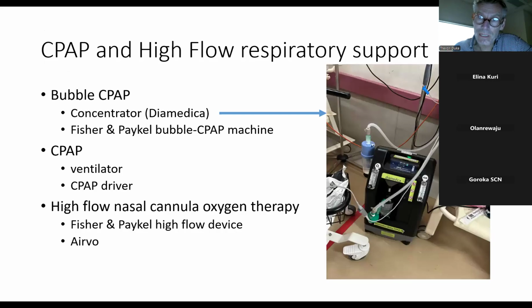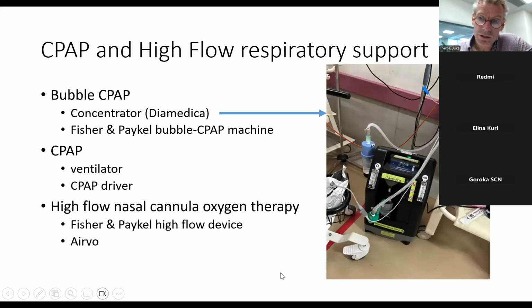This is the Diamedica machine that is being introduced in many hospitals. It's a similar machine to the grey one that we previously had used more in children than neonates, but most of these are going to be delivered to special care nurseries and neonatal units in provincial level hospitals. I'll talk quite a bit about how these work, but there's an oxygen concentrator that extracts atmospheric air, removes the nitrogen, and produces both oxygen and air. Using this type of machine, you can blend the oxygen, which means that you don't have to give 100% oxygen to preterm neonates.